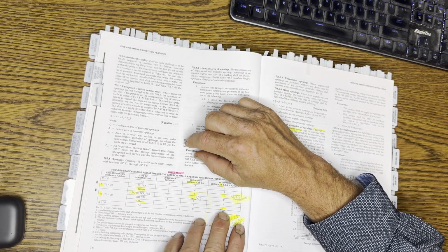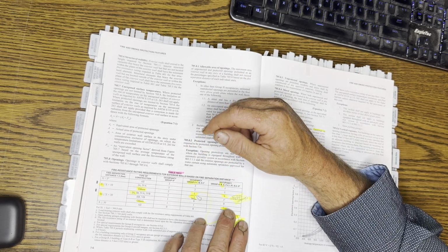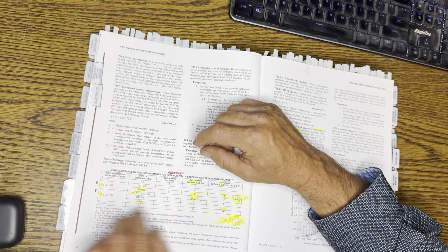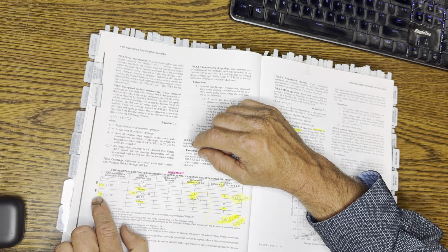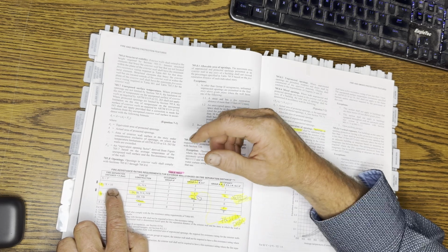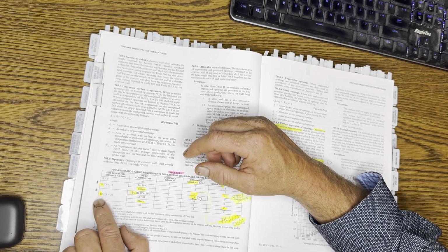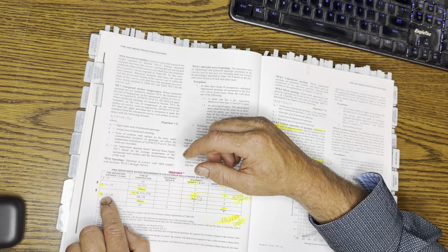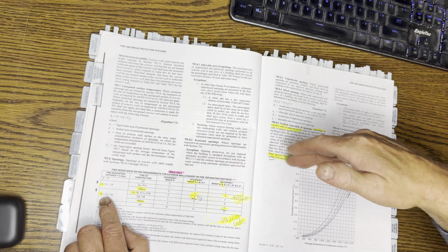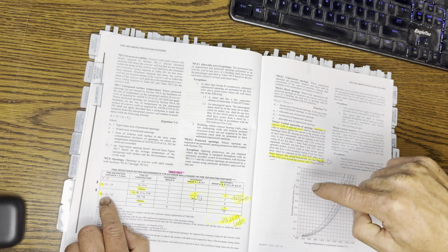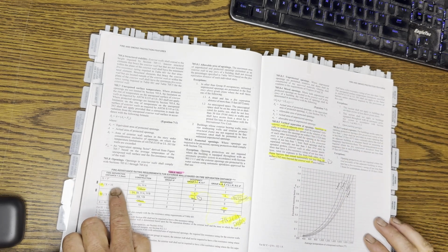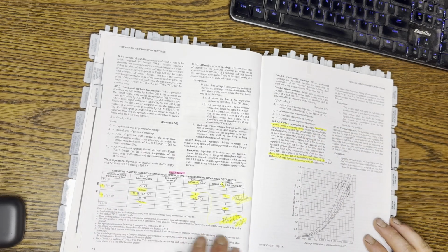So I don't want to take the time to read all this, but what it comes out to be is 20 feet's the magic number. That's when you transition. This 10 feet, that's to a lot line. It is not to a building. It's to a lot line, and the lot line separates buildings on a typical lot. So the actual distance from building to building is 20 feet. So that's the takeaway from this chapter.